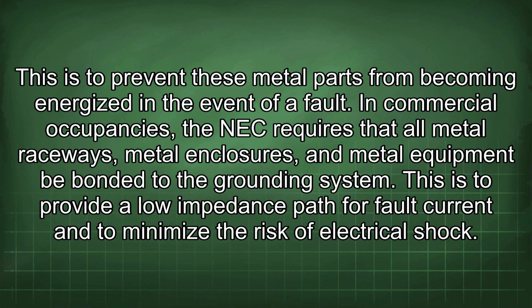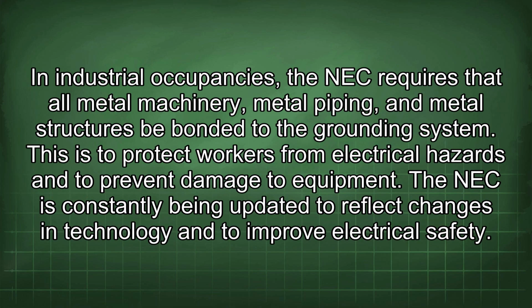In commercial occupancies, the NEC requires that all metal raceways, metal enclosures, and metal equipment be bonded to the grounding system. This is to provide a low impedance path for fault current and to minimize the risk of electrical shock. In industrial occupancies, the NEC requires that all metal machinery, metal piping, and metal structures be bonded to the grounding system. This is to protect workers from electrical hazards and to prevent damage to equipment.